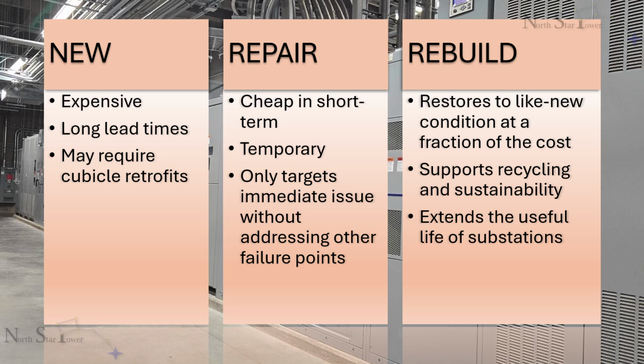It also supports recycling and sustainability goals, keeps your system design consistent, and helps extend the useful life of your equipment. Not every breaker can or should be rebuilt, but when it's a viable option, it saves time, money, and waste. And when combined with a solid maintenance and testing program, rebuilds can give a plant decades of reliable protection. A good plan is to have spares tested and, if necessary, rebuilt before planned shutdowns, so reliable backups are available if in-service breakers fail.